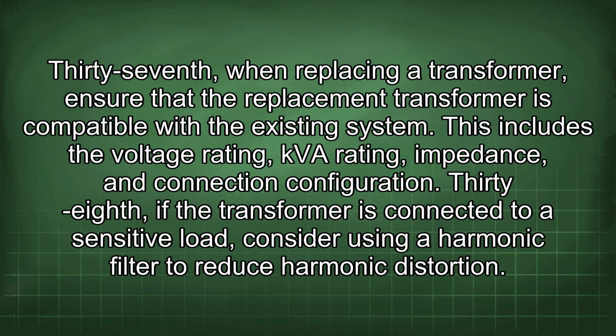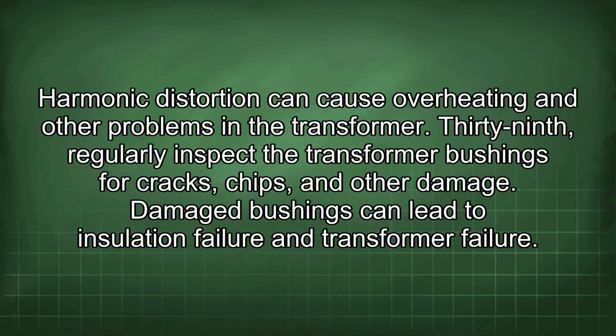37th, when replacing a transformer, ensure that the replacement transformer is compatible with the existing system. This includes the voltage rating, kVA rating, impedance, and connection configuration. 38th, if the transformer is connected to a sensitive load, consider using a harmonic filter to reduce harmonic distortion. Harmonic distortion can cause overheating and other problems in the transformer.